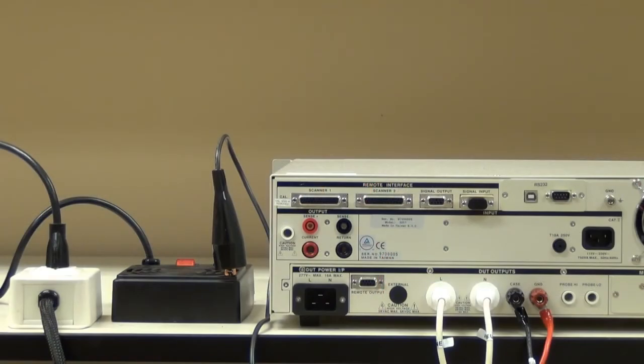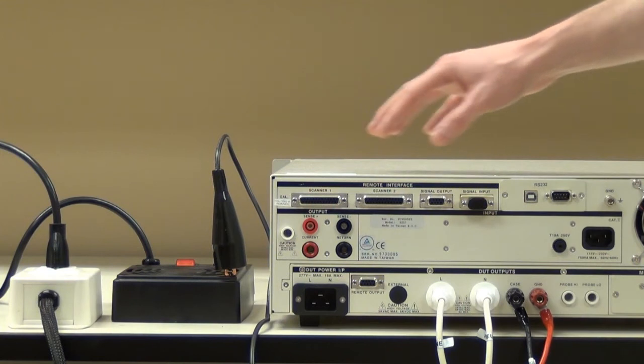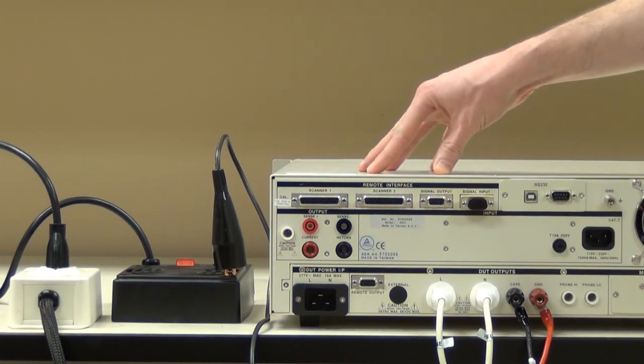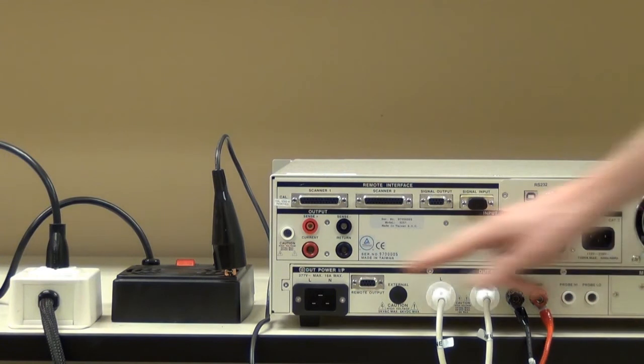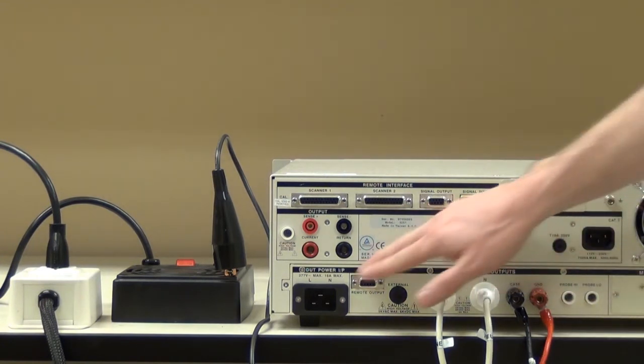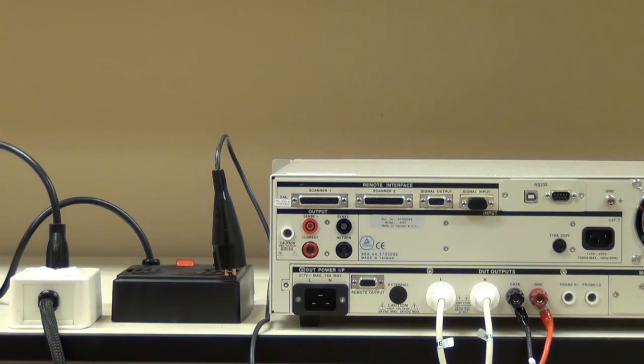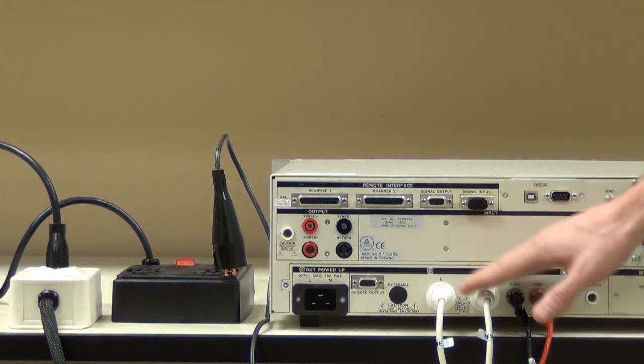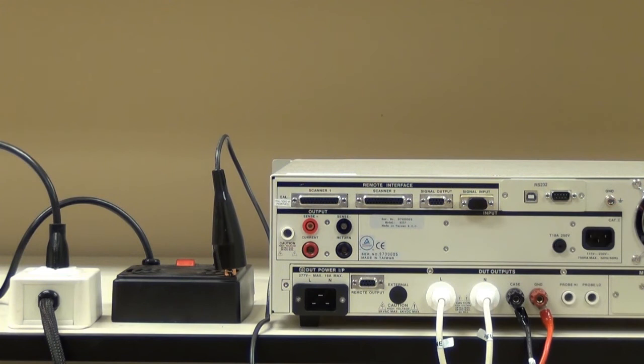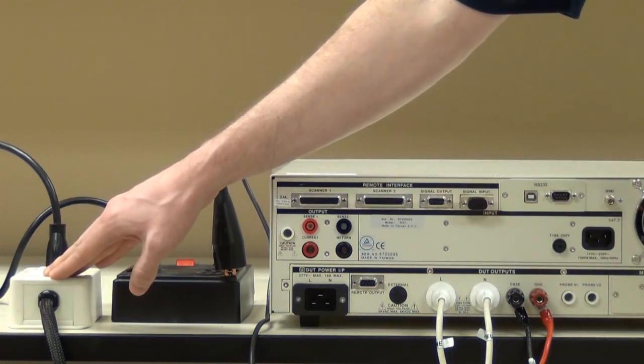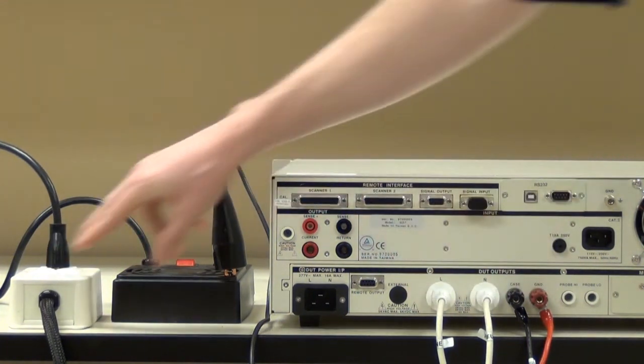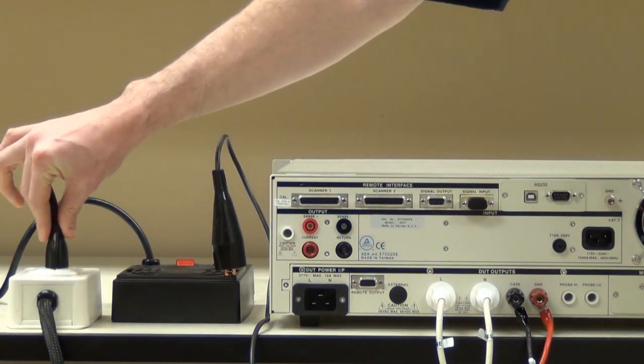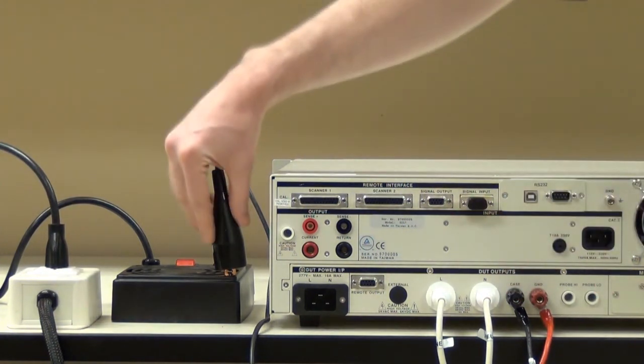The final recommendation we're going to make here comes into play if you have an 8206, 56, 07, or 57 instrument. That's because those instruments have what we call the LLT card for line leakage and functional run connection. The advantage of this card on these DUT outputs is that it allows you to run the full gamut of testing from just these connections: line, neutral, case, and ground. For example, you can see here that I have a product connected up to the adapter box. So line, neutral, and ground go to the adapter box where I have the product plugged in. Case is my return point, which I have on the chassis.